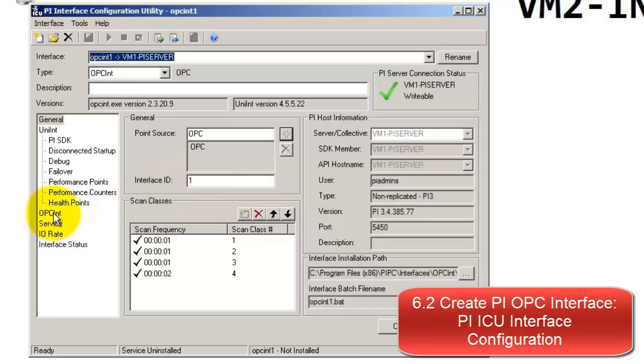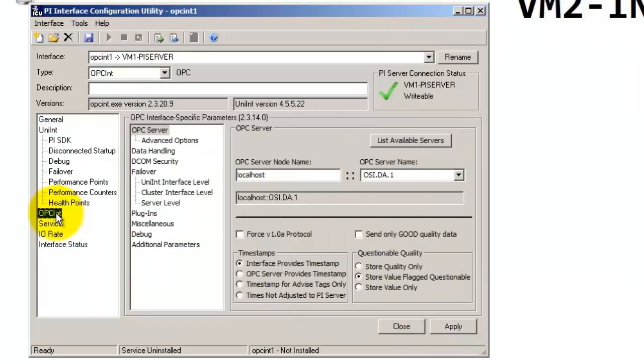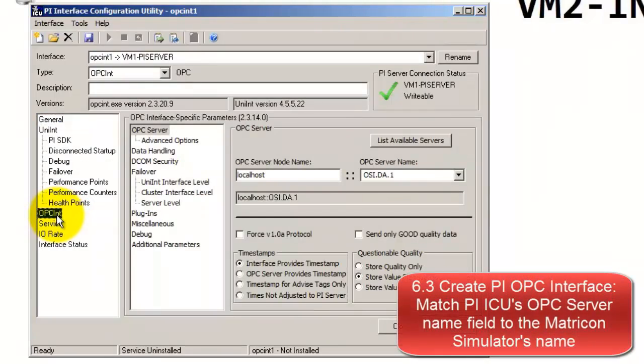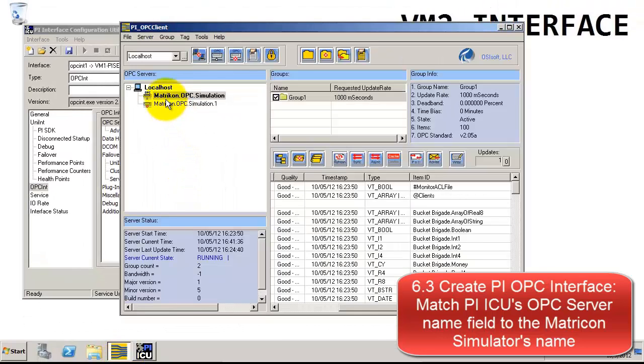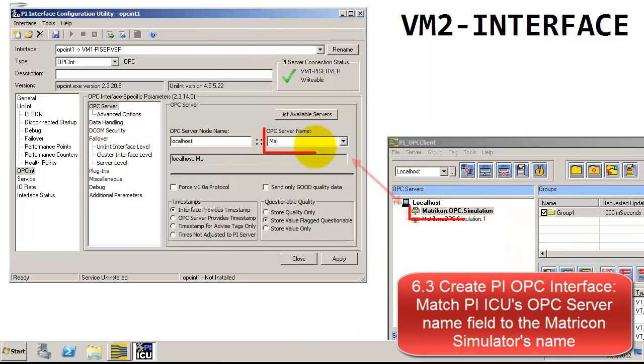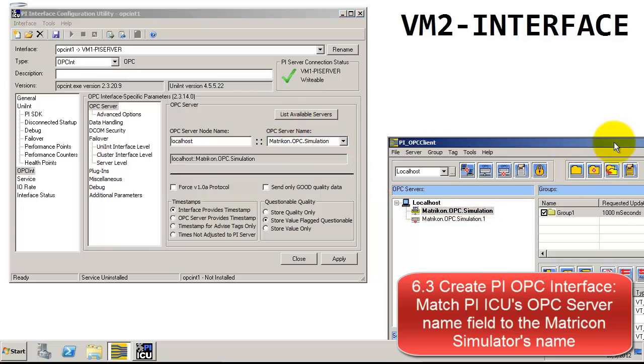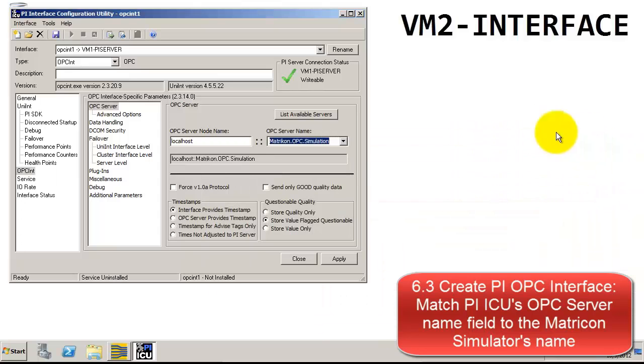That was all on the General tab. Now we're moving to the interface-specific tab, which is OPC-INT on the left. On this tab, we need to specifically indicate the OPC server name — the current default needs to be changed. To get the OPC server name, we can use the OPC Client tool we looked at earlier. The OPC server name is Matrikon.OPC.Simulation, so make sure to type this in exactly as such. To save these changes, hit the Apply button at the bottom before moving to the next tab.